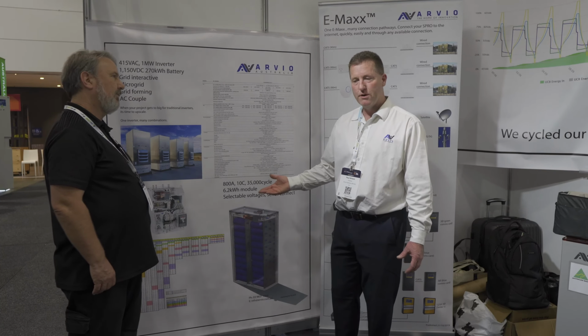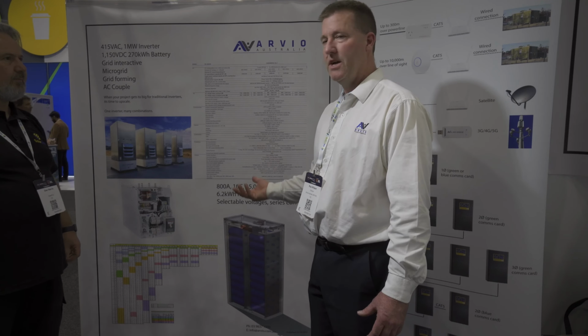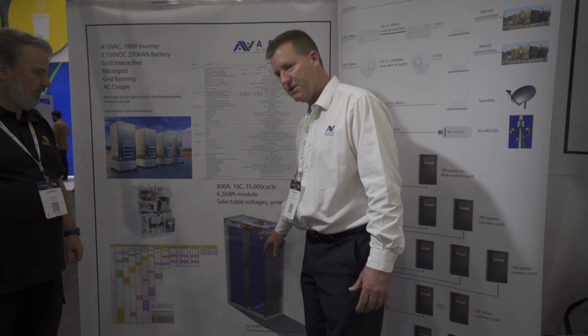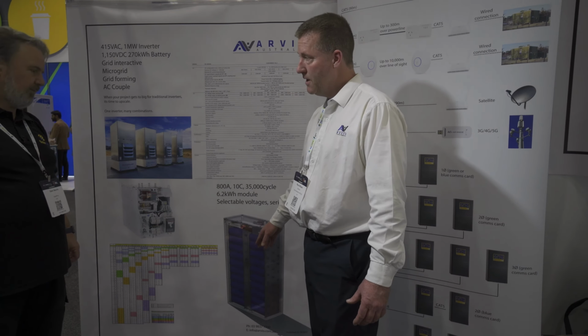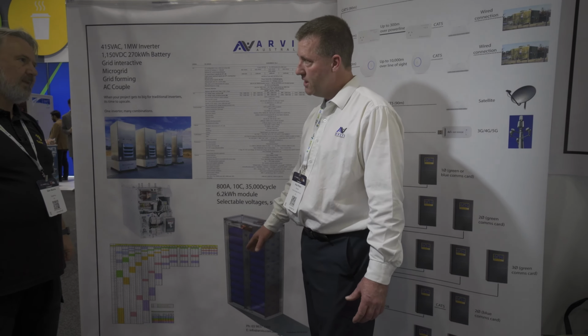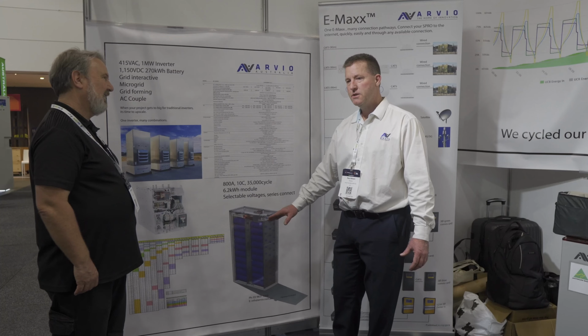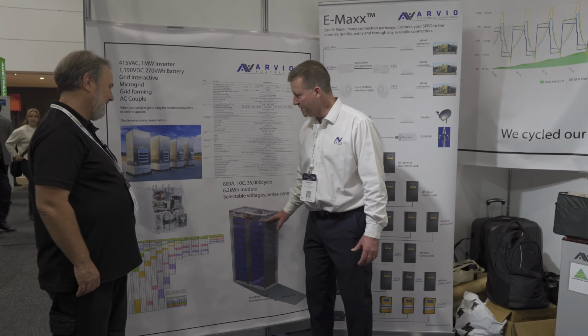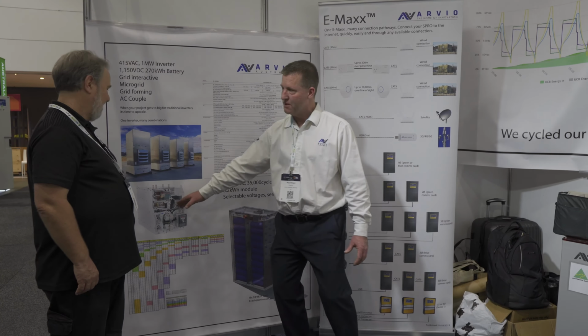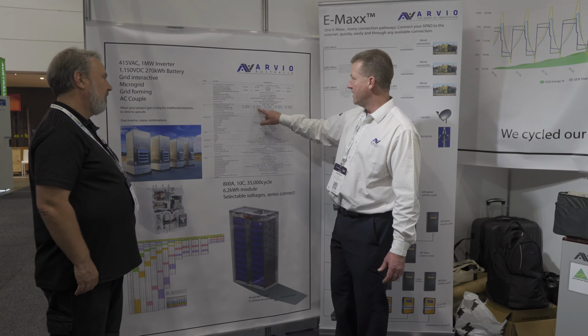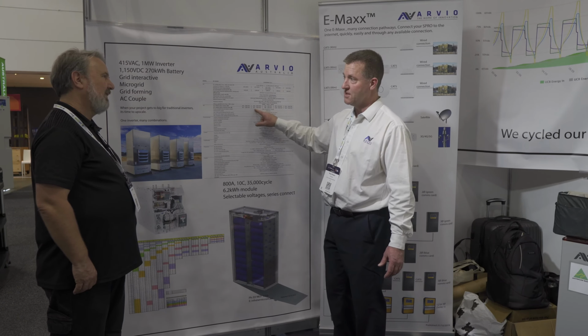Then we thought we need an inverter which can actually give us that amount of AC power. So each one of these modules can produce 60 kilowatts of power from 6.2 kilowatt hours of energy storage, so it's 10C, a 6-minute charge, 6-minute discharge. If we series connect enough of these together, we reach the voltages that this inverter wants to see, which is around 900 volts to 1200 volts DC.